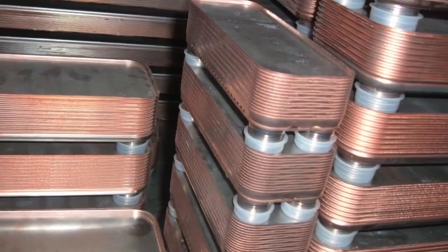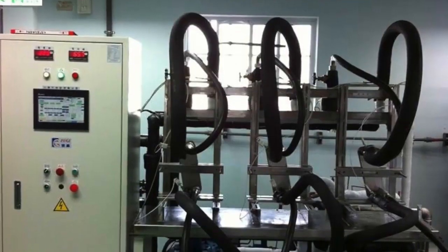We must bear in mind that the oven is filled with exchangers. They remain there for a specific number of hours at the melting temperature of copper or nickel. The copper or nickel melts, and through capillarity on the stainless steel, it flows into the contact points. After a certain period of time, the exchangers are extracted and ready to be used. Clearly, all heat exchangers go through pressure testing procedures.